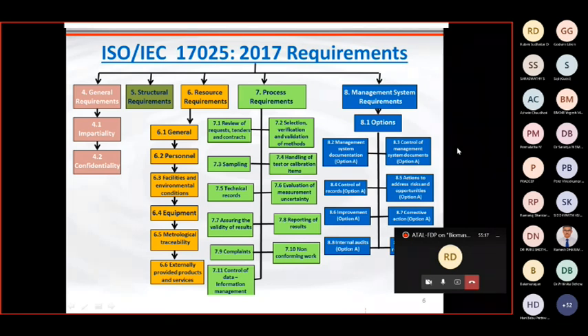Then comes resources. To run a laboratory, you require people, you require facilities. Facilities are water supply or drainage system or compressed air supply, then environmental conditions, air conditioning of your laboratory. If it is a clean lab, maintaining cleanliness of the laboratory. So you know what the environmental requirements of a laboratory are. Then equipment: the testing or calibrating equipment or instruments, measuring instruments, all those are covered under equipment. Then metrological traceability. Wherever you have a measurement, wherever you have a measurement uncertainty which is likely to affect your final results of calibration or results of testing, they all require to be periodically calibrated.